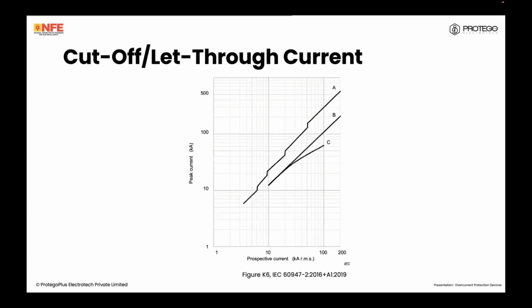Now, there are certain other characteristics. There is a cutoff or let through current. See, a lot of these circuit breakers and fuses, OCPDs, are what we call current limiting. What this means is that they will not allow the full fault current to actually pass through the circuit.